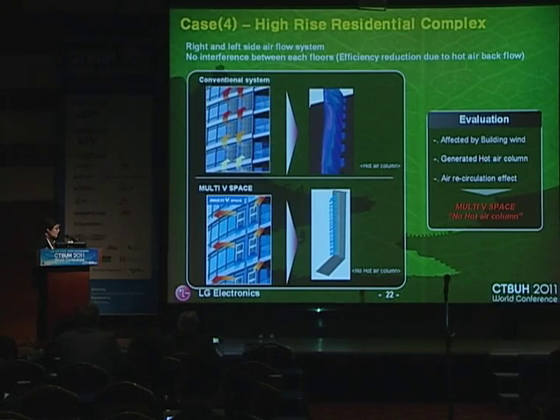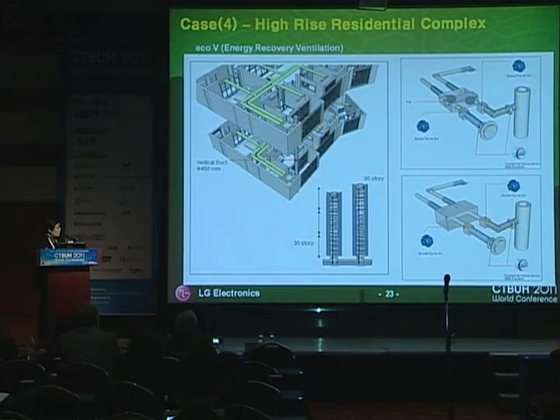If you use a conventional air-cooled heat pump system, a heat column occurs in this building. So at high-rise levels, heat pump performance is very reduced, but Multi V Space blows air out to the right and left, so the hot column effect does not occur. So the building performance is very high. And in this building, the energy recovery ventilating system is applied.